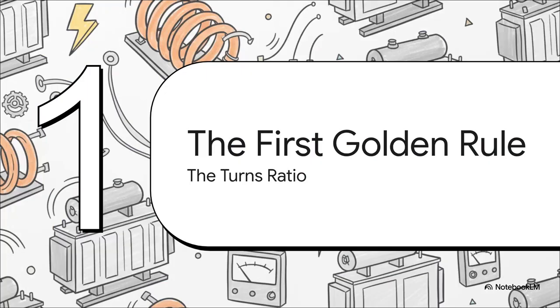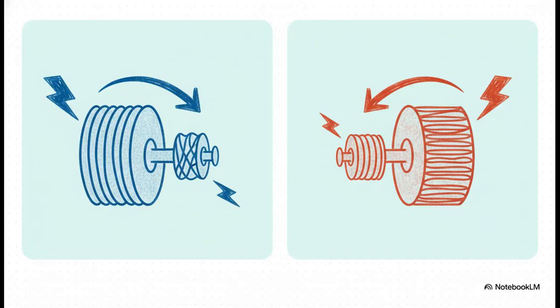Okay, that's great. But how do we control exactly how much the voltage changes? This brings us to our very first golden rule, and I'm telling you, this is the key to almost every transformer calculation you'll ever face. It's called the turns ratio. The turns ratio is actually super simple. It's just comparing the number of times the wire is wrapped around the primary coil to the number of wraps on the secondary. Now, in our world, the world of industrial controls, we almost always use a step-down transformer. And that just means it has fewer turns on the secondary coil, which gives us a lower voltage on the secondary side. Step-up transformers, they do the opposite, and you mainly see those used for sending power over long distances.